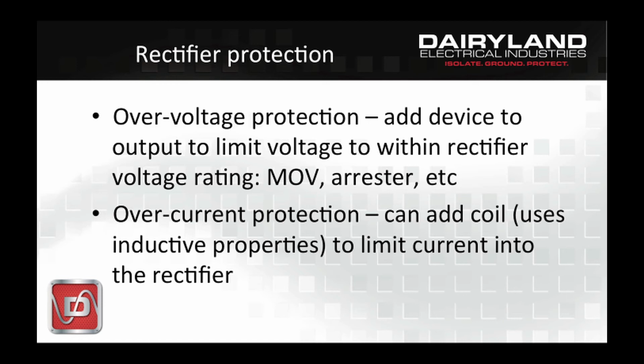So overvoltage protection is limiting the voltage on the output of the rectifier to deal with the reverse polarity, and we use metal oxide varistors or arresters, spark gap arresters, something like that. For overcurrent protection, this one's a little trickier, but sometimes various methods involving coils, which actually is using inductance to accomplish something useful, to limit current, have been done, say on the negative lead of the rectifier. In fact, Dairyland at one time produced a rectifier protector product that did this very function of protecting overcurrent and overvoltage for rectifiers.